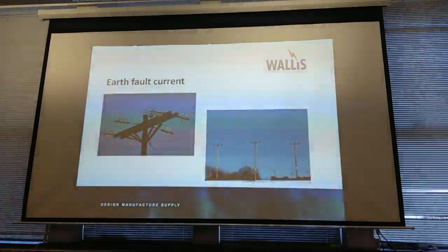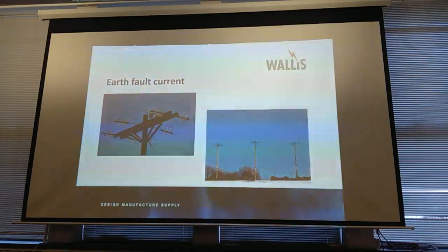Whereas the nice wood pole system that we have around East Midlands, West Midlands, the vast majority of the country, has 1, 2, 3 wires, no earth wire, no return wire. So all the fault is going to be going to the general mass of Earth via the Earth system that you're designing. So you need to know what's happening in the feeder network, if that makes sense. So there's a lot to it.